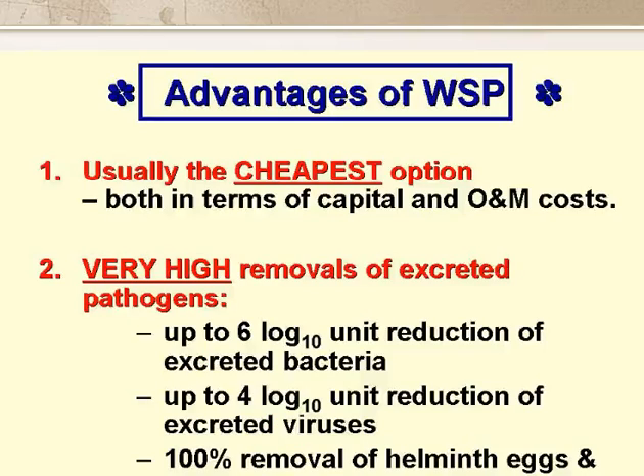Ponds have many advantages. They are usually the cheapest, both to construct and to operate and maintain. They can achieve very high removals of excreted pathogens — for example, up to a 6 log unit reduction of excreted bacteria. That's a removal of 99.9999%, with each of these 9s being a significant figure. Up to a 4 log unit reduction of excreted viruses, a 100% removal of helminth eggs, and generally over 90% removal of protozoan cysts and oocysts.